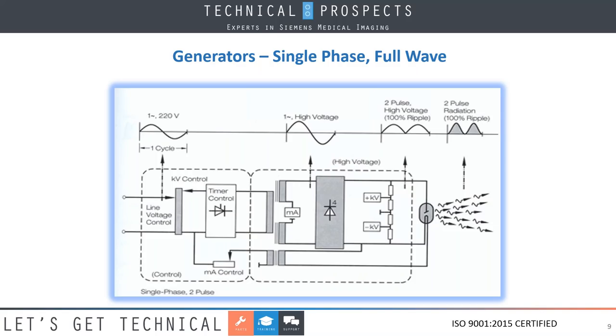All right, so let's take a look at some of the generators here, and you can kind of get an idea of what we're talking about. Notice over here on the primary side, which is on the left-hand side of your picture, you see the KV control and MA control for the circuits. You see your split secondary as you move over further to the right with the MA meter in the middle of this. You see the timer control on the primary side, and then you see the rectifier that goes through right before the X-ray tube, giving us the full wave rectification.